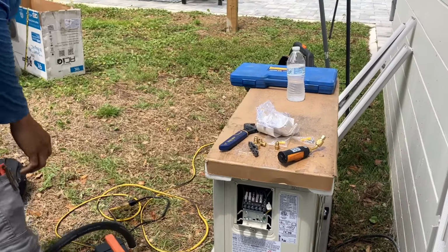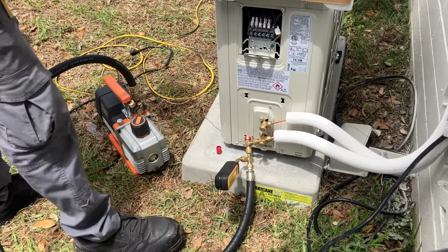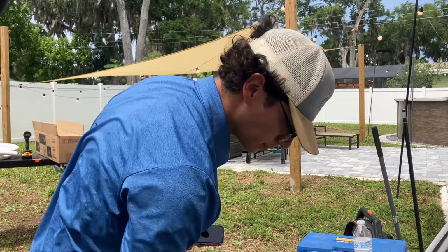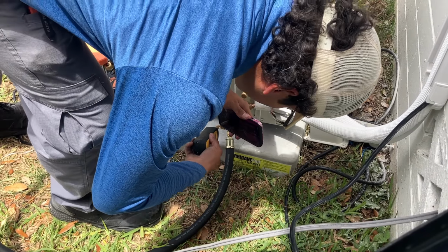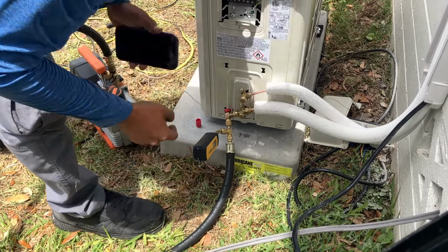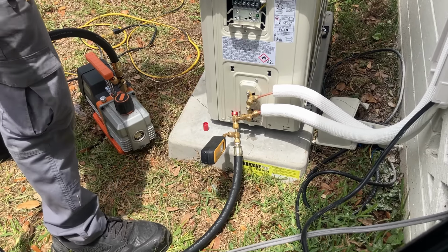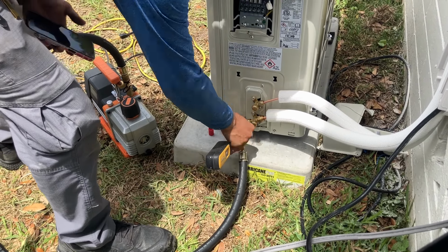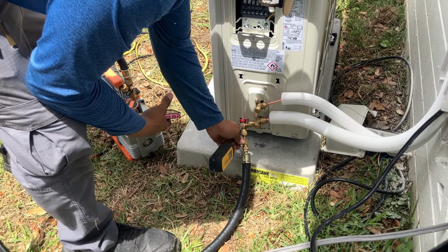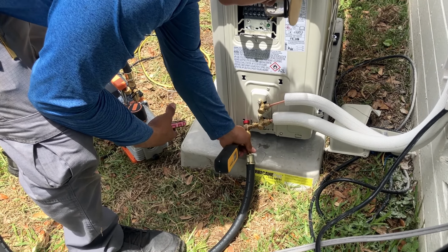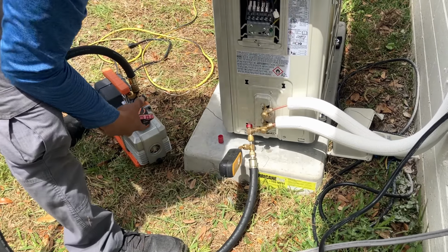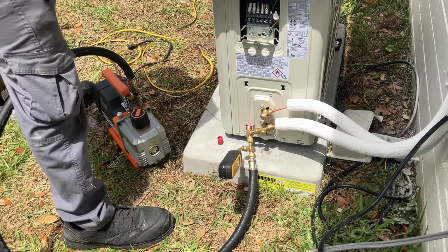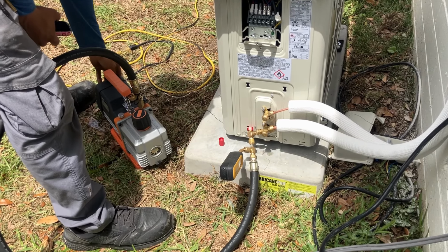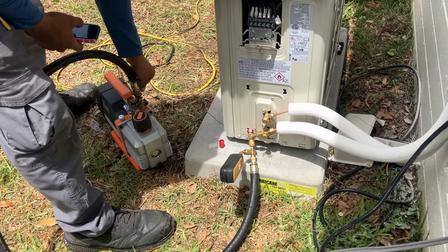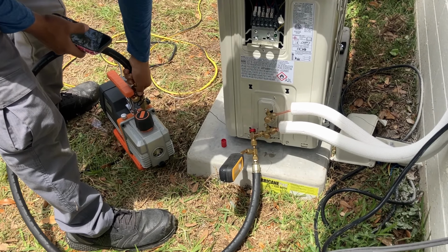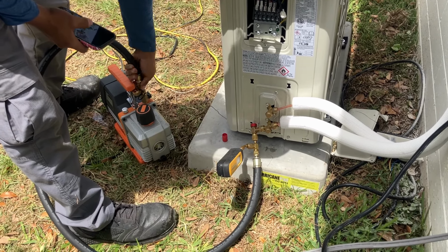The Testo one's pretty good. Yeah, I'm not a fan of Testo anymore. I went last year with the JB Climate Class probes, phenomenal. I was finding with the Testo smart probes I was losing range with the Bluetooth connection. If I went inside, for example, it dropped off, and it takes a while to reconnect. But the Climate Class probes are very nice. The temperature clamp-on probes were a problem because the plastic was breaking, but they fixed that, and the range is excellent. I could be in a 3 or 4 story apartment building, outside, and my guy upstairs can have the probes on the supply and return lines, the supply and return ducts, and it's nice.